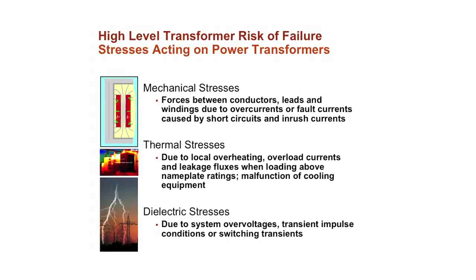Okay, so again, we have the mechanical, thermal, and dielectric. The mechanical has to do with the forces in the windings. This is caused by overcurrent, fault current. It could also be caused by inrush current, by having many inrush currents. And then thermal stress is due to overheating of the windings or overheating of metal parts in the transformer. That could be due to long-time loading, or something wrong with the cooling, or it could be just the way it was designed and built. And then you have dielectric stresses. This is some kind of overvoltage, such as lightning. You could have switching transients. So I'll go through the background of all of these.